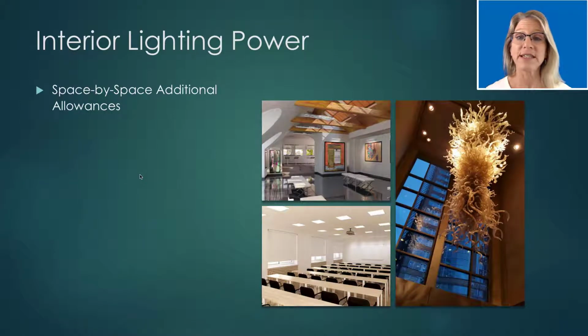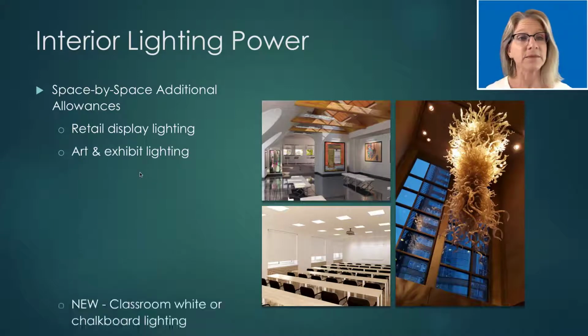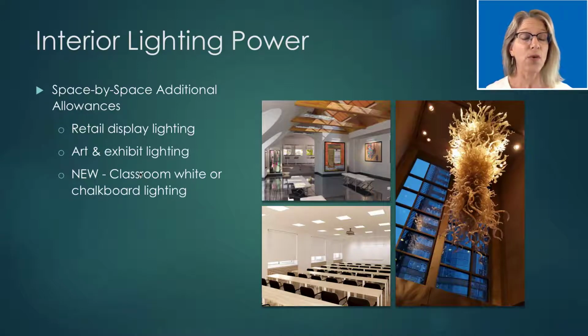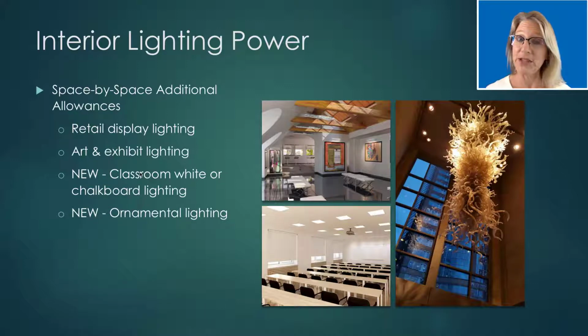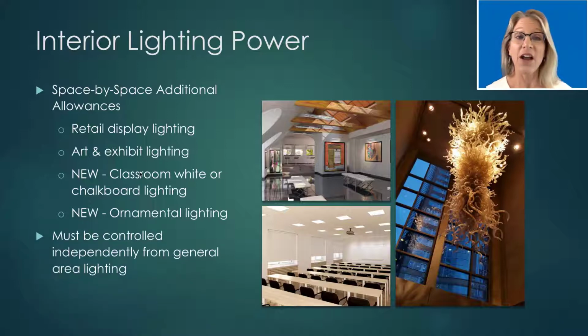Additional lighting power allowances in the 2018 WSEC include retail display lighting and art and exhibit lighting. There's a new allowance for lighting over a classroom whiteboard or chalkboard, and for ornamental lighting. Note that ornamental lighting includes chandeliers, wall sconces and lanterns, neon and cold cathode lighting, moving lights, light colored panels, that sort of thing. To qualify, the lights have to be used in a decorative manner that does not serve as display lighting or general lighting. They also must be controlled, all of the additional allowances, independently from general area lighting.